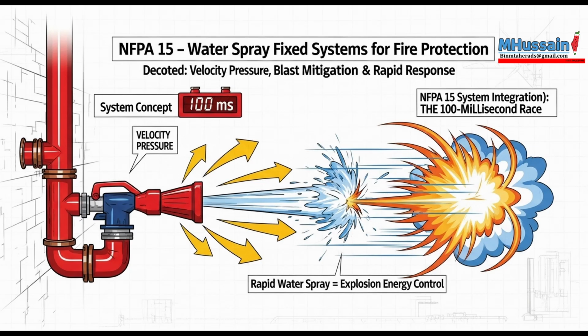Okay. For the math itself, the standard points to the Hazen-Williams formula for friction loss in pipes, 8.5.1.1. Any specific rules about the C values used in that formula? Yes, engineers have to use the C values from table 8.5.3.0 and use the correct one for the pipe material and condition. For example, new copper or stainless steel gets a C150 because it's very smooth inside. Right. But black steel pipe, which is common in wet systems, gets a more conservative C120. This accounts for slightly higher friction loss. The engineer can't just pick a higher C value to make their pressure numbers look better. Got it. Stick to the table.